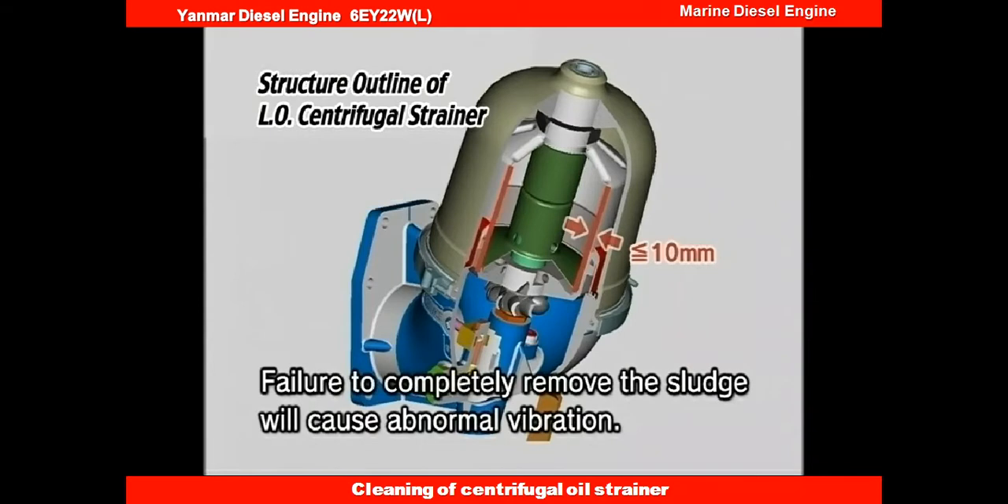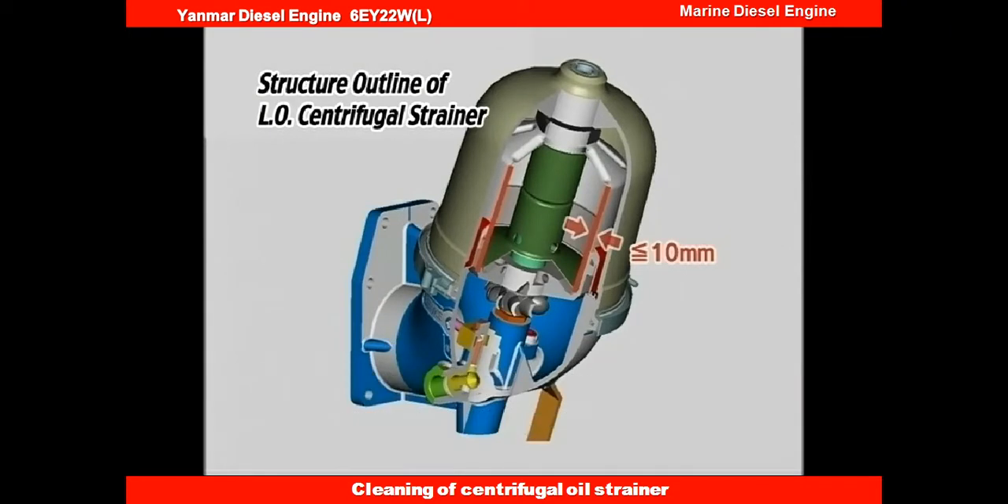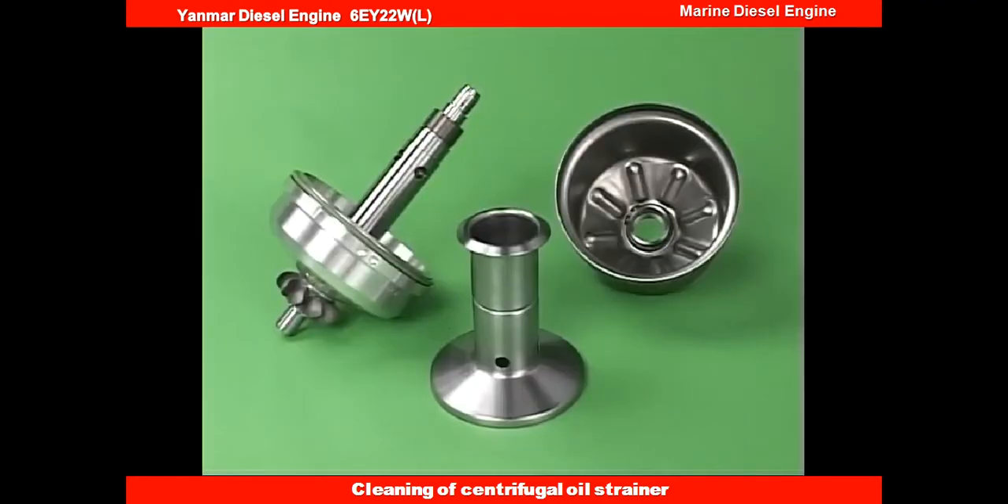Remove the sludge on the inside wall of the rotor. If the thickness of sludge deposition is over 10mm, cleaning will not be effective. Clean the rotor body and rotor cover, and check for clogging of the nozzle.